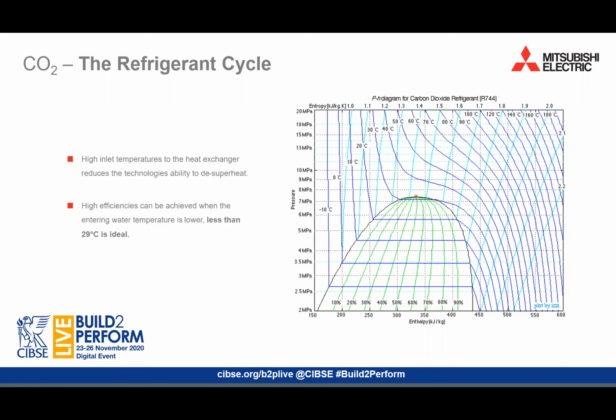So now let's consider an inlet temperature of 10 degrees into the gas cooler. Again, at point 1, this is the point where the refrigerant enters the compressor. Pressure increases from 40 bar to 120 bar, and temperature from approximately 10 degrees to 110 degrees. Point 2 again is when the refrigerant enters into the gas cooler. However, now the inlet water temperature to the heat exchanger is 10 degrees. And now we see that the gas cools all the way down to approximately 10 to 12 degrees Celsius. This means that the delivered enthalpy between points 2 and 3 through the heat exchange cycle is hugely increased to roughly 180 kilojoules per kilogram.